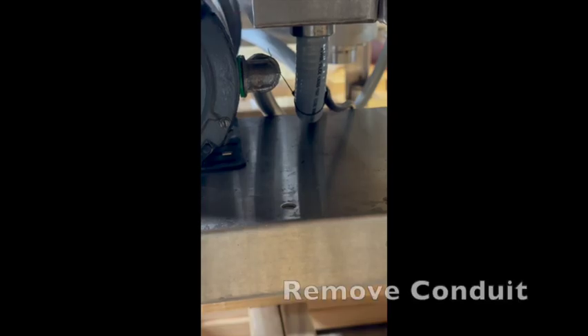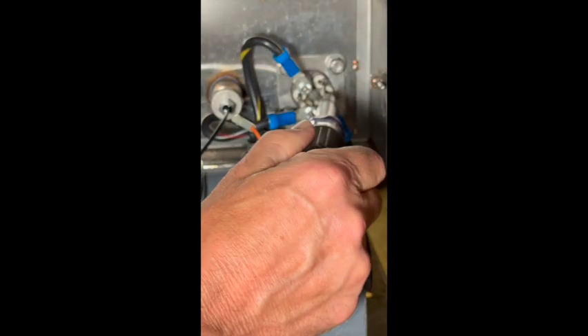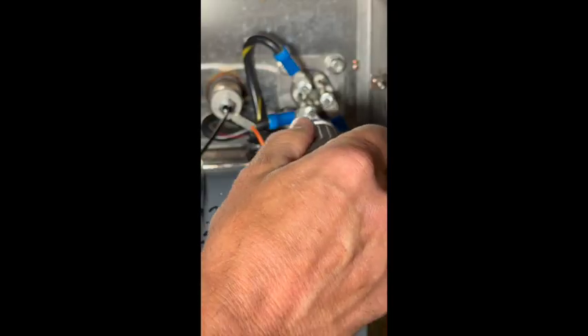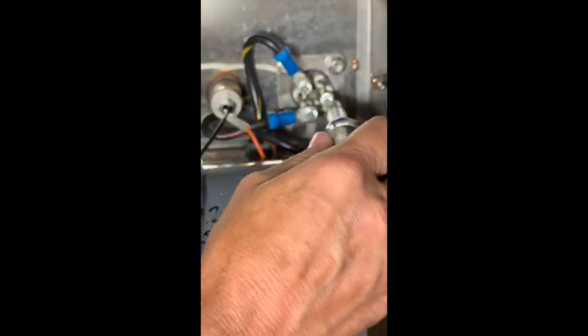Here's probably the biggest problem I ran into during this installation: trying to pull that probe wire through that conduit. The conduit that has the wash heater wires in it is pretty maxed out. So my process was to remove the conduit in order to get that probe wire through. It's a pretty straightforward process. To remove the conduit at the heater control box, just remove the nuts that hold the conduit in place. I did have to remove all the wires connecting to the heating element.